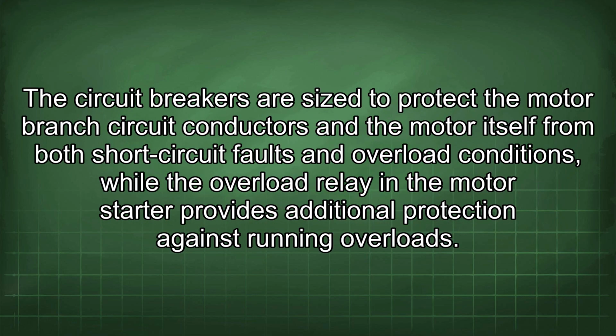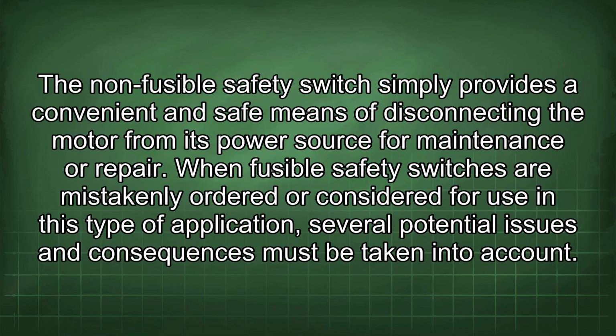The circuit breakers are sized to protect the motor branch circuit conductors and the motor itself from both short circuit faults and overload conditions, while the overload relay in the motor starter provides additional protection against running overloads. The non-fusible safety switch simply provides a convenient and safe means of disconnecting the motor from its power source for maintenance or repair. When fusible safety switches are mistakenly ordered or considered for use in this type of application, several potential issues and consequences must be taken into account.